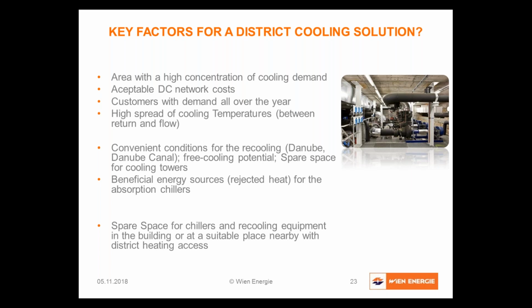The most challenging topic for district cooling is always the recooling. If there is the possibility for river water cooling, it's perfect. If not, you have to think about open cooling towers, whatever. If there are some energy sources like rejected heat, it makes sense to build up absorption chillers. If you have to pay a lot for the heating energy, it makes no sense to run any absorption chillers.